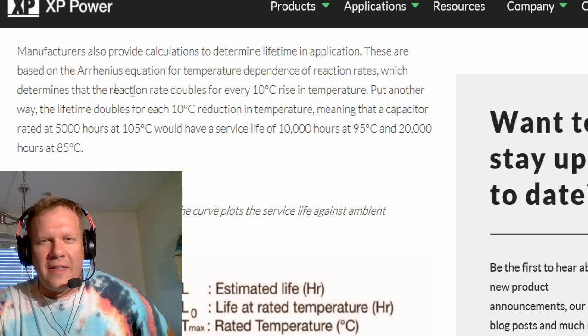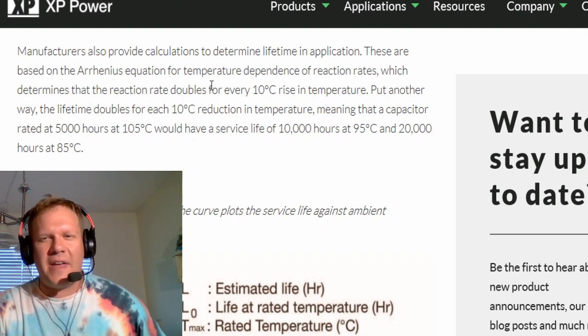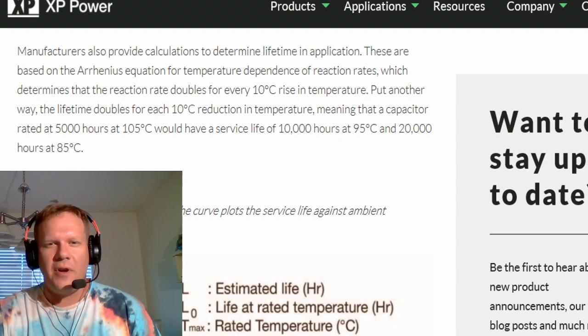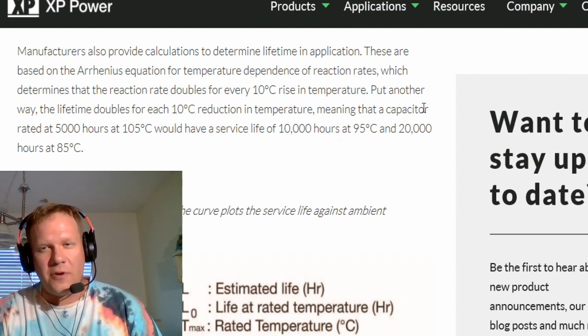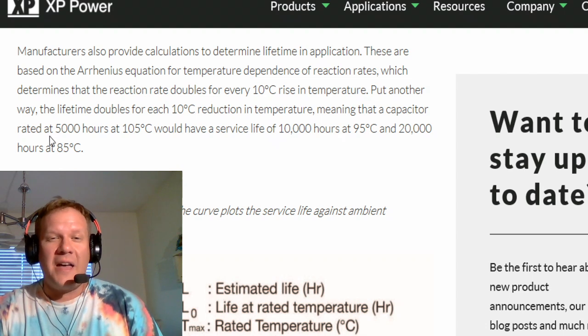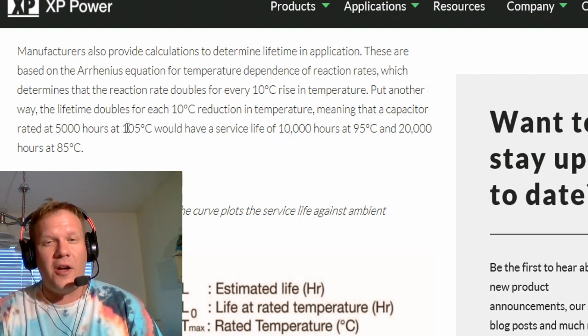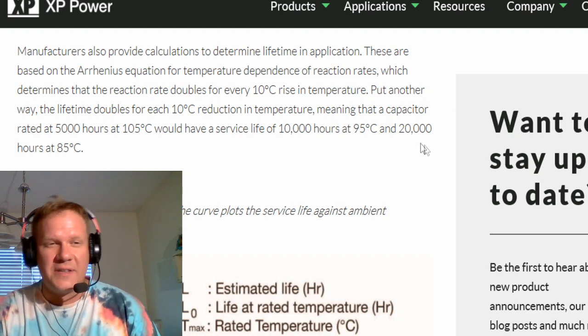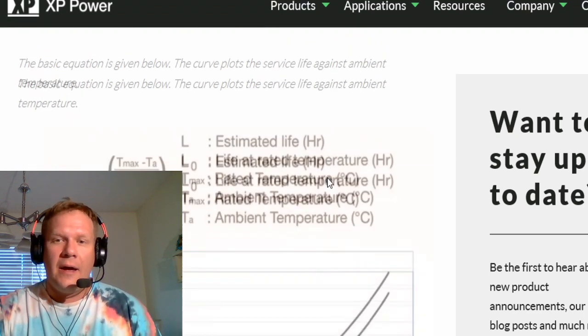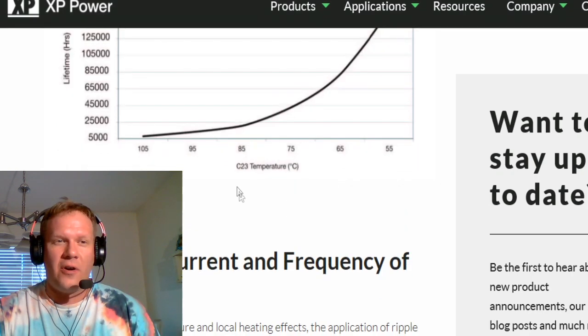Basically, the reaction rate doubles every 10 degrees Celsius rise in temperature. Put another way, the lifetime of a capacitor doubles for each 10 degrees Celsius reduction in temperature, meaning that a capacitor rated at 5,000 hours at 105 degrees Celsius, if you drop that down to 95 degrees Celsius, it doubles the life. Then if you drop it down to 85 degrees Celsius, it doubles the life again to 20,000 hours.